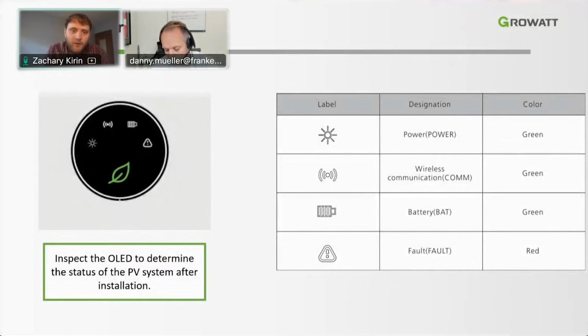Excellent. So once you get the inverter put onto the wall, you'll see the OLED has 4 lights to communicate to the user the status of various system workings. So here we can see the leaf means that power is on. The inverter is not operating, but it is at least powered on. The power light here will show the power is communicating with the inverter. The wireless communication is shown as well. And then the battery, when the battery is communicating with the inverter as well, you'll see green here.